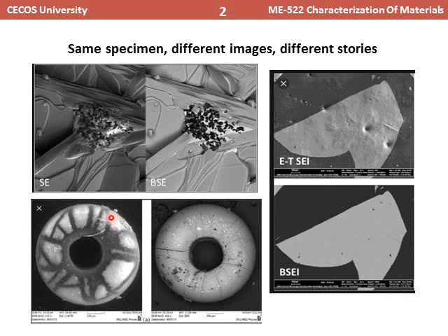So surface morphology can be viewed by the secondary electron, you can see that there are islands of some objects on the surface of the donut, whereas the backscattered electron penetrates a little bit more from the surface, and you can see that only the major cracks are visible, because these cracks are much more in depth.